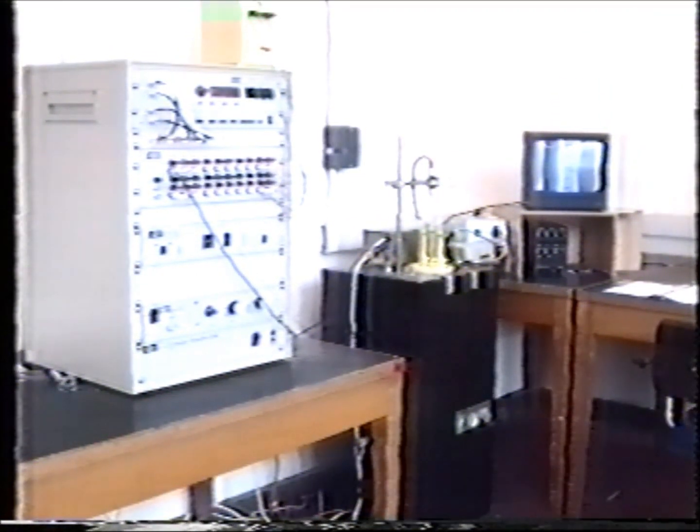Numerically, the biggest task of the Quality Assurance Laboratory is the calibration of thermometers. Some 3,500 per year are calibrated. All types of mercury-in-glass are dealt with, including ordinary, maximum, minimum, soil and sea thermometers. Most are new and are tested for conformance to the Met Office specification.